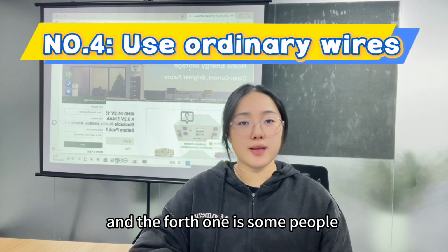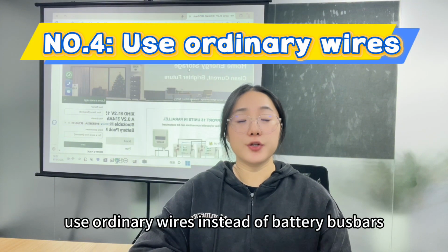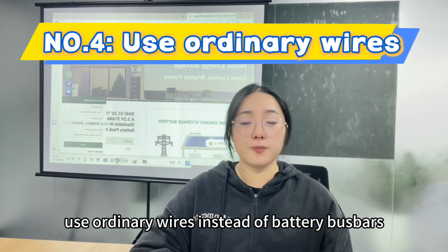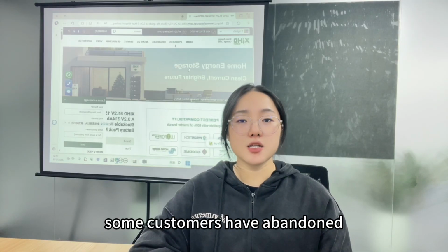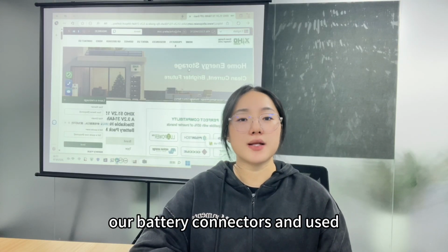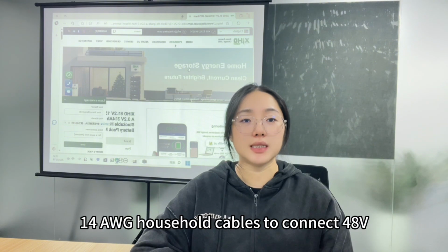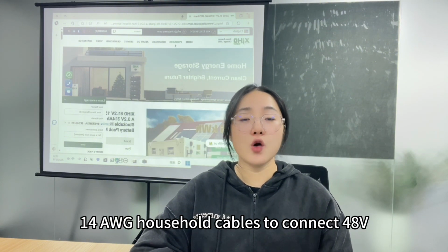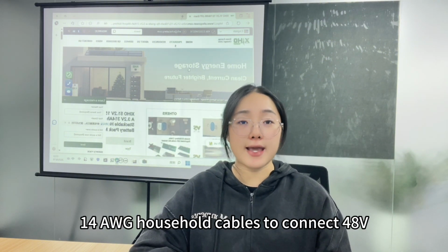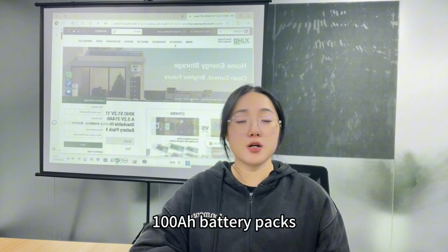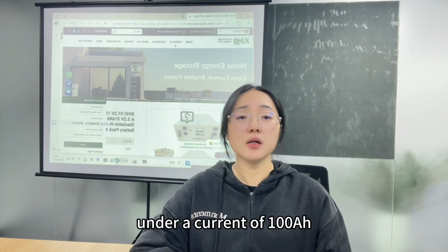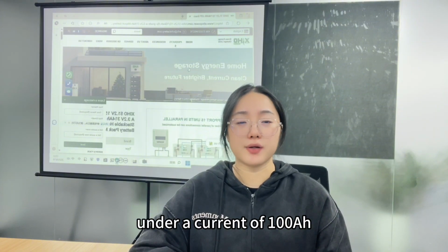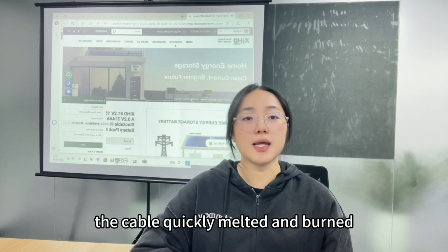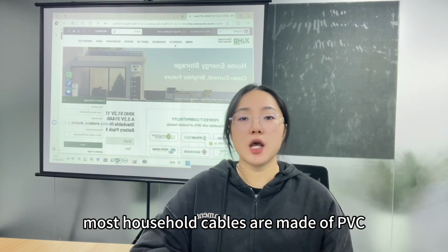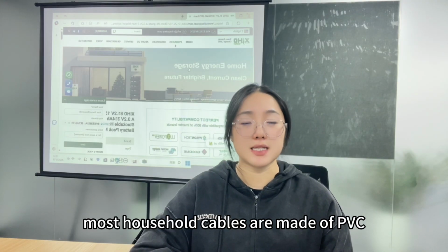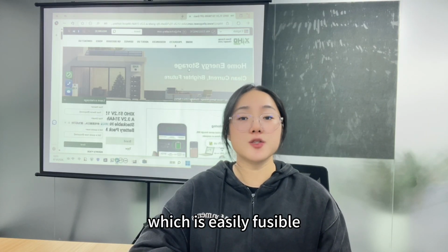The next mistake is some people use ordinary wires instead of battery bus bars. Some customers abandoned our battery connectors and used 14 AWG household cables to connect 48 volt, 100 ampere battery packs. Under a current of 100 amperes, the cable quickly melted and burned. Most household cables are made of PVC, which melts easily.